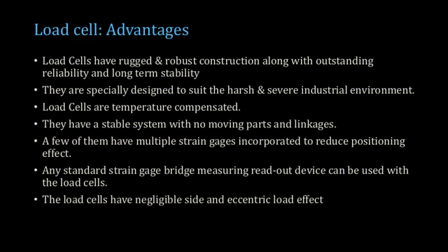Now some of the advantages of load cells are that they are rugged and robust in construction, they have good reliability and stability, they are specially designed to suit the harsh and severe environment, and they are temperature compensated. Strain gauges may get affected by temperature, but load cells in general are temperature compensated.